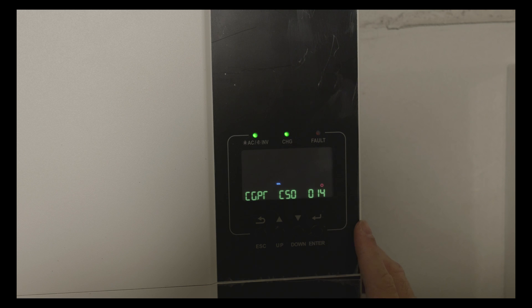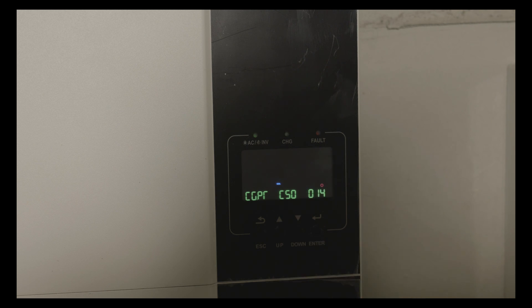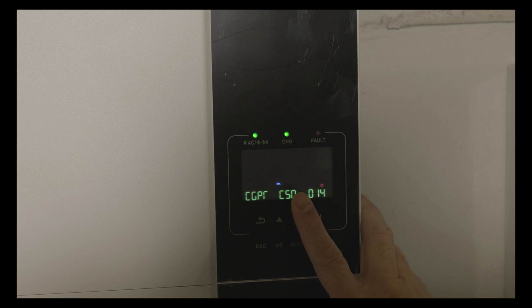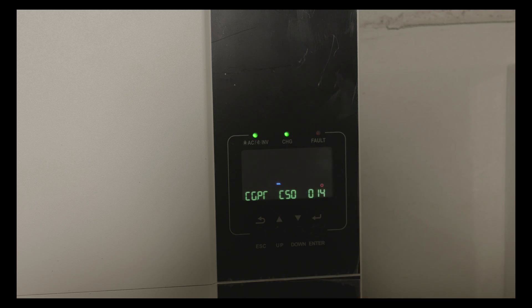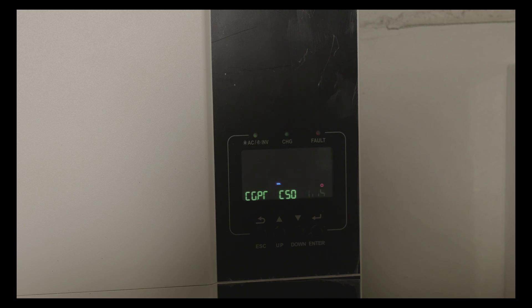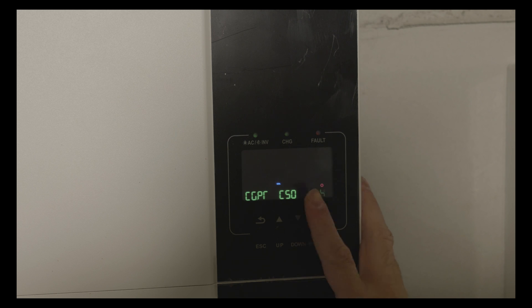Option 14, charger source priority, I've selected CSO. CSO option is solar energy will charge battery as first priority, and then utility will charge batteries only when solar energy is not available. Again, I'm charging my batteries at night, so this is the option that I've chosen.